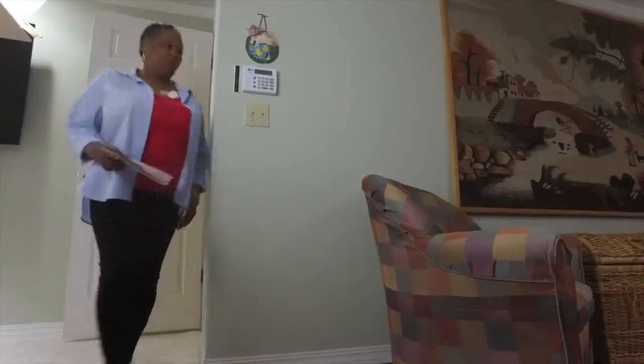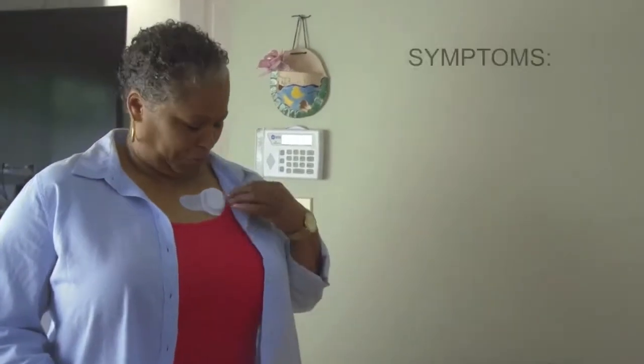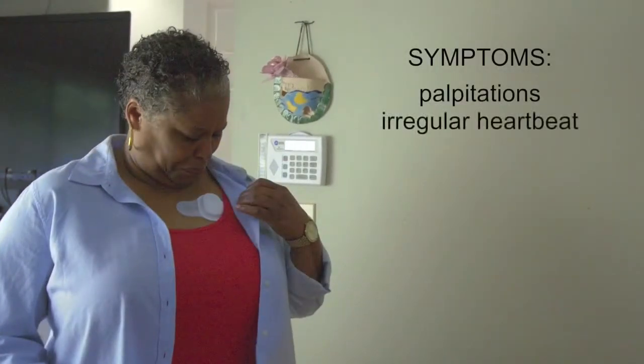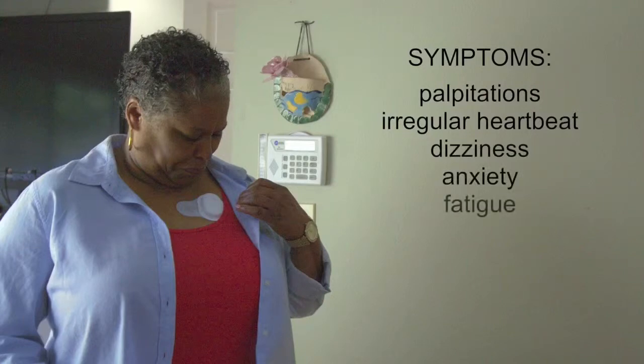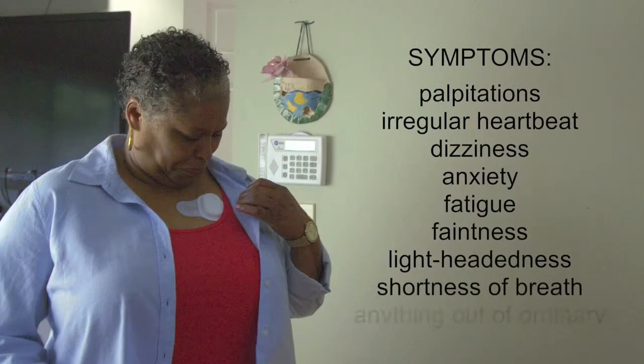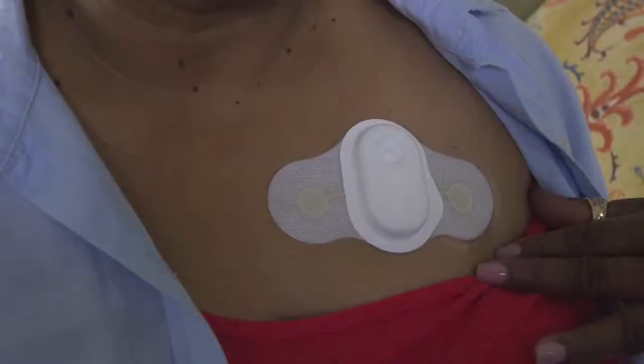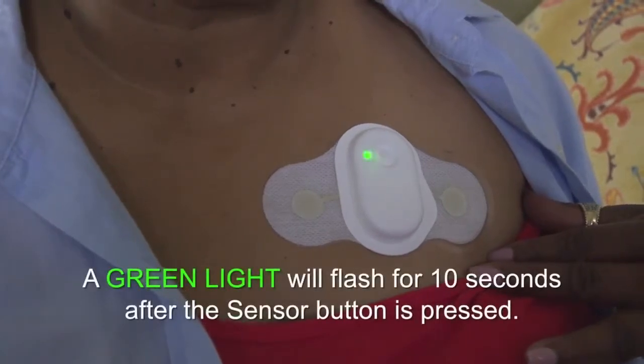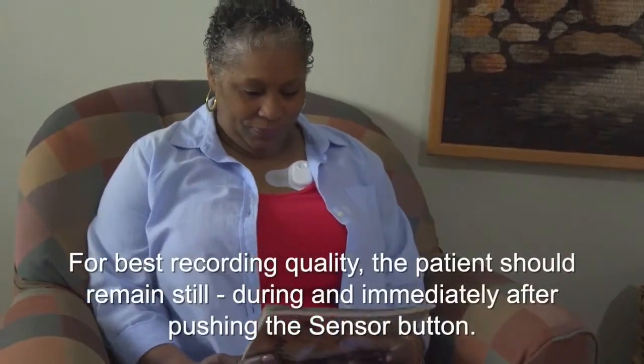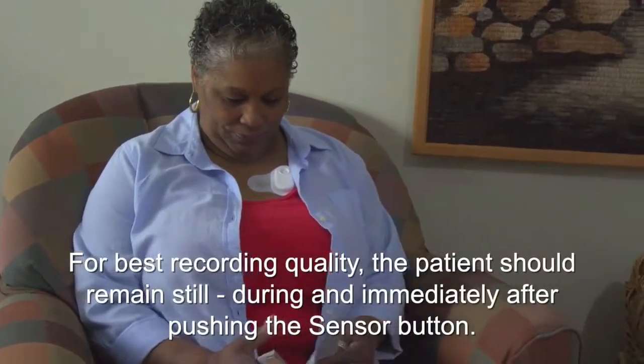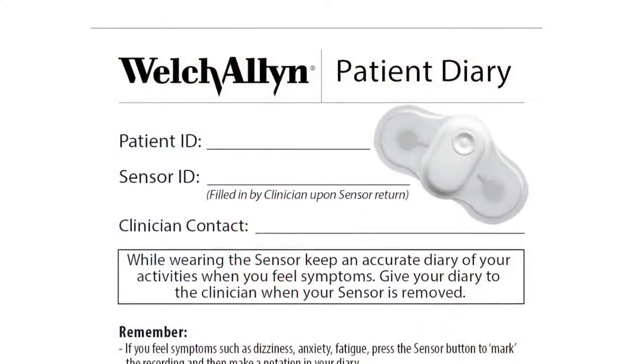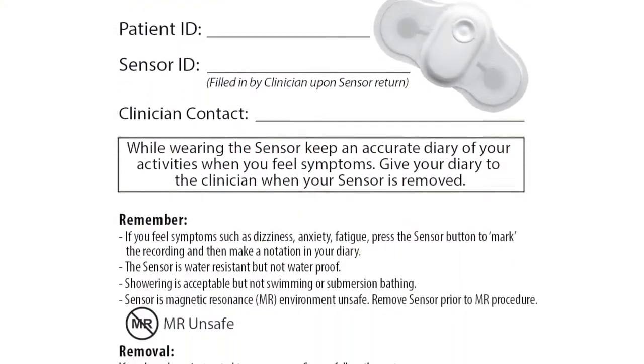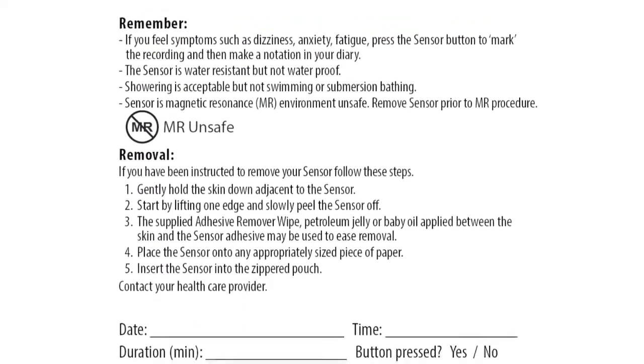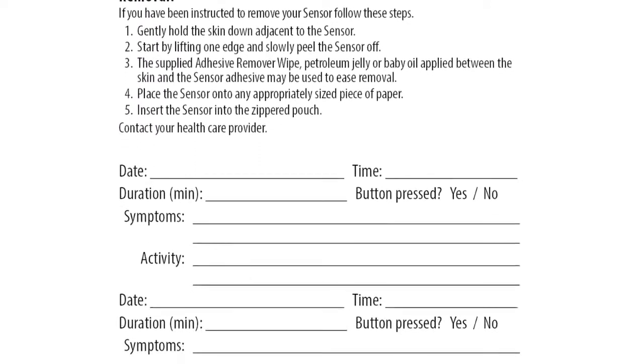Patient trigger button. The patient should be instructed to press the sensor button if they experience symptoms such as palpitations, irregular heartbeat, dizziness, anxiety, fatigue, faintness, lightheadedness, shortness of breath, or anything out of the ordinary. A green light will flash for 10 seconds after the sensor button is pressed. For the best recording quality, the patient should remain still during and immediately after pushing the sensor button. Instruct the patient to write in the provided patient diary if they experienced any symptoms and push the button, particularly noting the date and time.